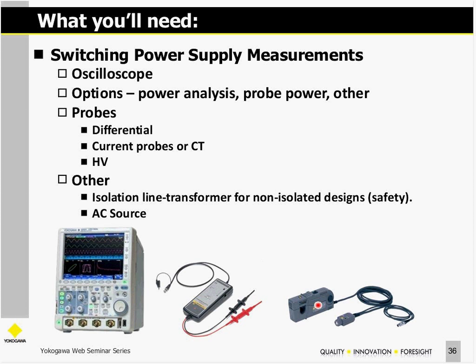If you buy a Yokogawa current probe, we could sell you a separate power supply that would allow you to move around a bit with your current probe. So we have passive probes, but also differential probes, current probes and current transformers, including a catalog of very accurate current probes and CTs, and we also have high voltage probes.